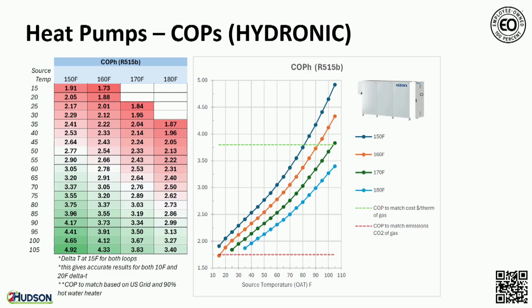Sometimes, when 2 numbers you can get, actually, you can get COP heating and you can get total COP. It's important to remember that because these are simultaneous products. If you start hearing numbers from people that COP of 9, COP of 10, they're probably telling you the combined COP. If you're getting numbers like 3 or 4, don't be like, oh, that's a bad heat pump. You're getting a realistic heating-only COP.